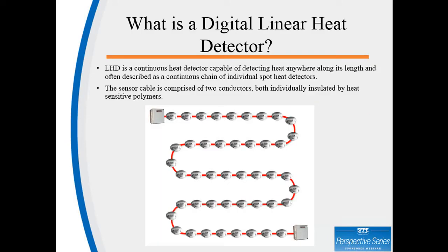What is digital linear heat detector? It can best be described as a continuous run of heat detectors. It is a detector anywhere along its length. The sensor cable is comprised of two conductors, both individually insulated by a heat-sensitive polymer. With Protectowire control gear, zones can be up to 10,000 feet or over 3,000 meters.